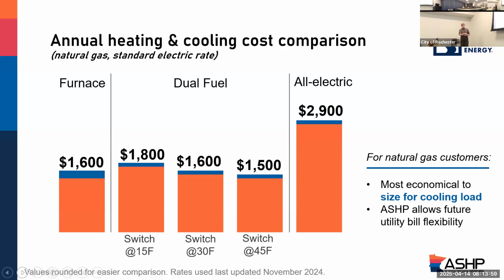On the sizing side, it's typically most economical to size the heat pump for the cooling load. You don't want to oversize it to take on more heating load, because you'll minimize operational costs better with higher switchover temperatures at this point in time.